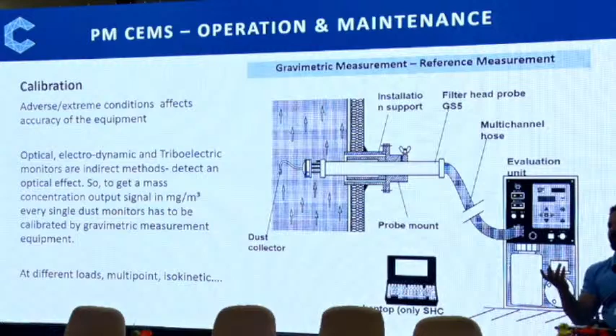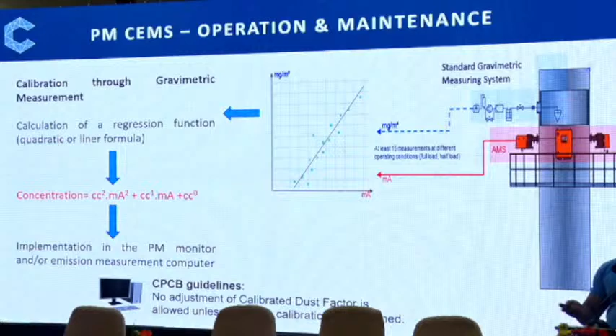The more readings we take, 9 points, 12 points, based on that we make a chart, and then you get a K factor. That K factor is used in the formula, and that is what you put in your software. So that is how we use gravimetric monitoring, and gravimetric monitoring gives you the reading in milligram per normal meter cube. We have a specific session on this. Gravimetric monitoring, which we use for calibration, is one of the most complicated and most important parts of the work. So we have a specific session of 1.5 hours here, where we will cover the set of calibrations, how we do the calculation, and what all we do. Then when we go to the plant site, that person will show with the equipment how it is done, and you calculate. So I am not going to focus more on the calibration part.